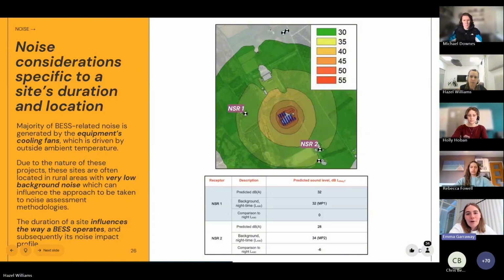That is really dependent on the size of the project, the duration of the project, and how it's being operated. There's no one size fits all as to which modelling parameters you're using, which can be quite difficult when reaching agreement with developers and councils on what should be modelled. For example, a 1 hour duration project would typically ramp up and ramp down quite quickly several times a day, because it's doing it over the space of an hour. Whereas a 4 or 8 hour duration scheme will be doing it a lot slower - the fans run at a lot lower effort and are therefore much quieter. So they're not comparable from that perspective.